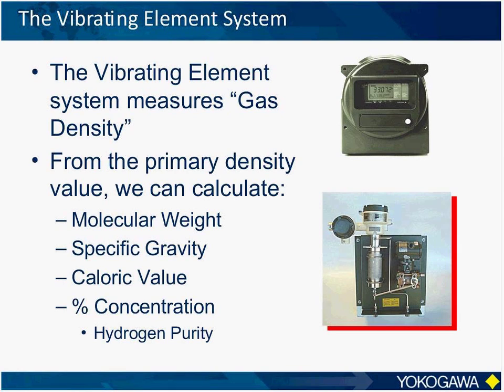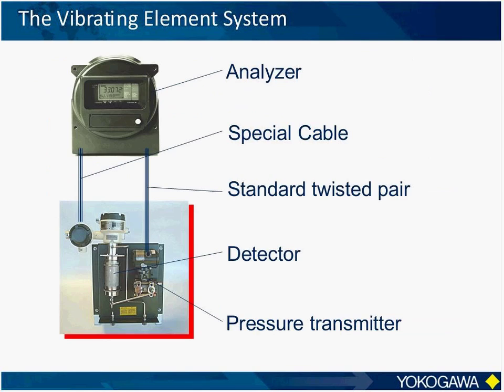Now, these are the components of a basic vibrating element system. Starting at the bottom, we have a detector where the actual vibrating element resides and where the gas that is being measured is connected. Also connected to the sample gas is a pressure transmitter that is used for real-time compensation. Now, these elements are all connected via cables to the analyzer, and it's the analyzer which receives the inputs, calculates, and then transmits the values via 4 to 20 milliamp signals.